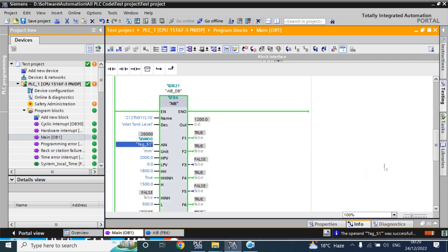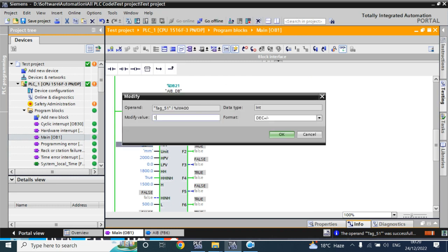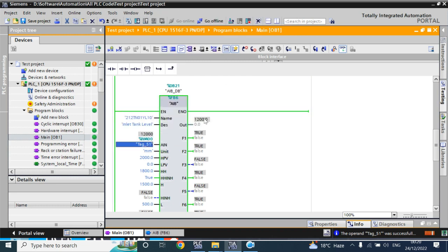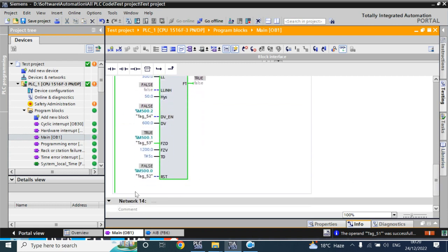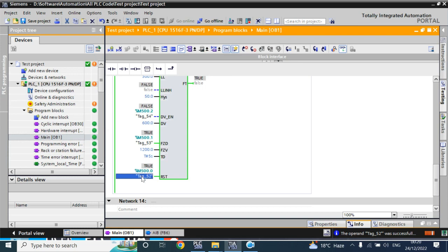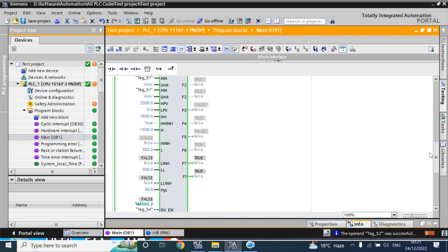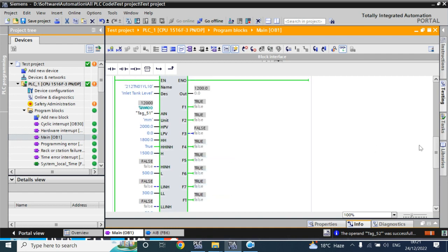Now I'll test with a value of 2600 to simulate an overflow. First I'll reset all the alarms back to zero. After resetting all alarms, the output is frozen to the freeze value.